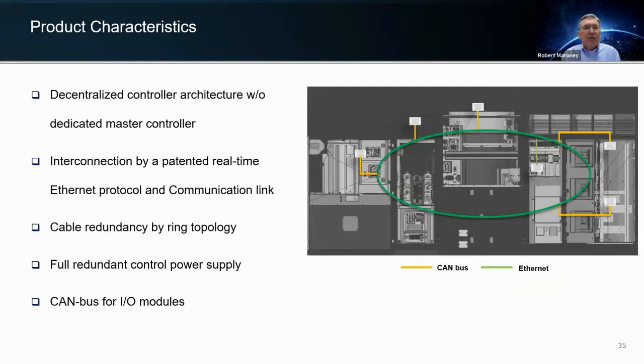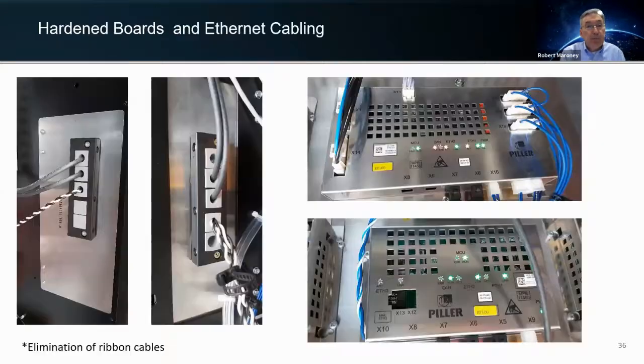So, characteristics: decentralized control architecture, okay, with no dedicated master controller. You have multiple controllers, so if any one component fails, we don't lose the entire system. We're using cable redundancy. We're getting rid of ribbon cables in our systems, using CAN bus systems and hardened printed circuit boards. So all the critical components are hardened within the UPS. How often have you seen a guy reach into a power electronics box, hook his sleeve on a printed circuit board, and yank a cable out of it?